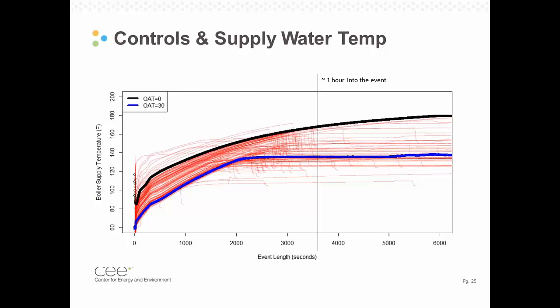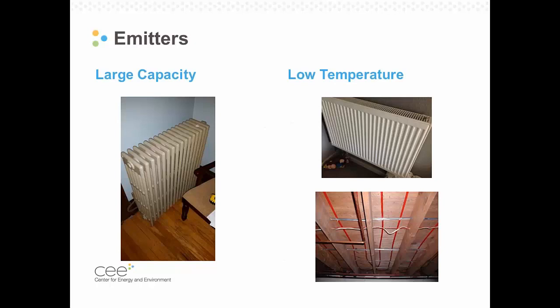What ends up happening here is that you are increasing the capacity as the event time goes along, so you're starting your heating cycle in a much more efficient scenario. In the plots, on a lot of those red lines, you can see the temperature drop dramatically when the cycle ends. Those cycles are ending on average somewhere between 30 and 60 minutes, so a lot of times you're not actually ever reaching that maximum boiler supply water condition before the house is satisfied. And so you're getting increased efficiency over even what that outdoor reset curve requests. That was a big benefit and a great control that we saw that really helped reach that 90% efficiency.